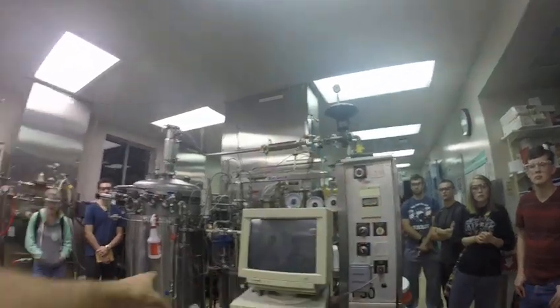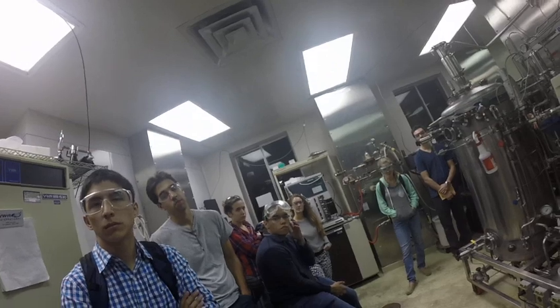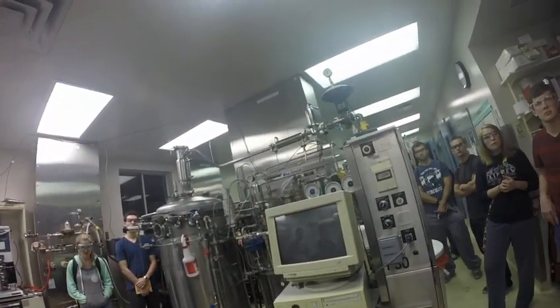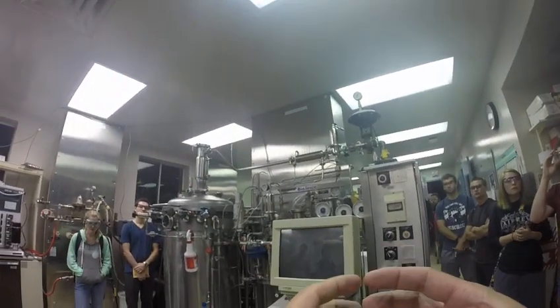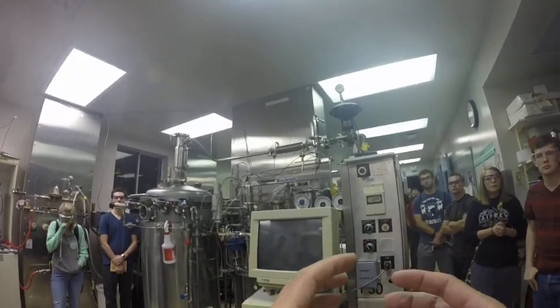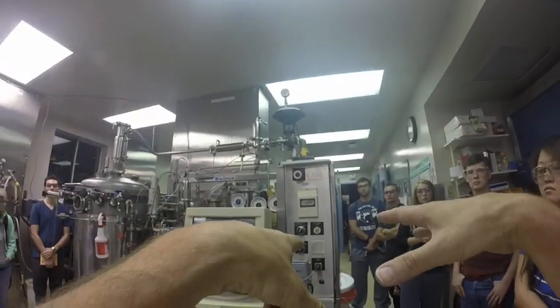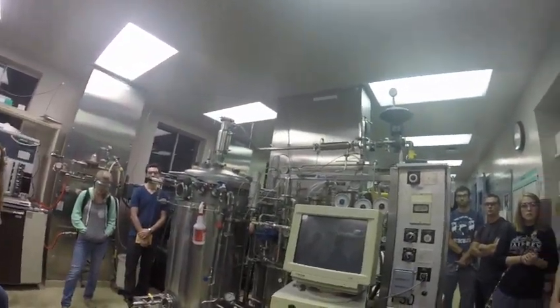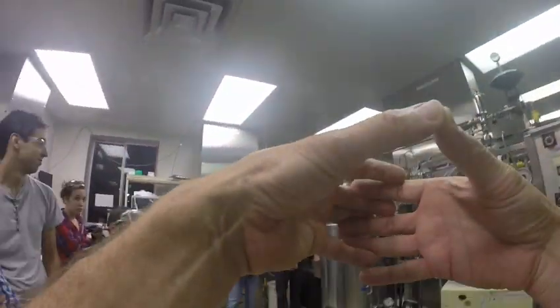The other thing is they're really nice to clean. That one down in the bottom there is a giant ball valve so that you can really open that sucker up and get stuff out. To give you an idea, on the mammalian cell reactor on the far side, we had trouble with the ball valve when we originally set it up in 1990, and it was being run with very high densities of microcarriers, and they would make a filter and clog the thing in there. So we had to replace it, and it cost us $7,000 for the stainless steel ball valve replacement. So it kind of gives you an idea.